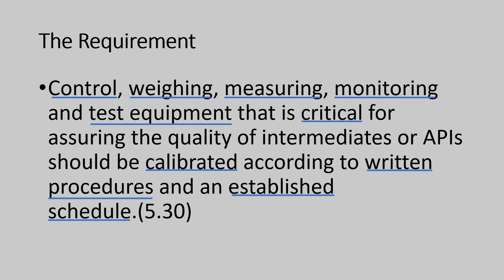It may not be necessary that all equipment is considered as critical for quality of output. How do you handle non-critical equipment? For example, there is a flow meter that shows the flow of process water into the overhead storage tank used for the process. However, there is a control on the overhead storage tank for checking the water level which is critical. So the flow meter to the storage tank may not be in the list of critical equipment. Another example is a secondary pressure gauge on the steam line which, with additional pressure gauges at the user point listed as critical, may also be classified as non-critical. This way, risk assessment would separate the critical and non-critical equipment.